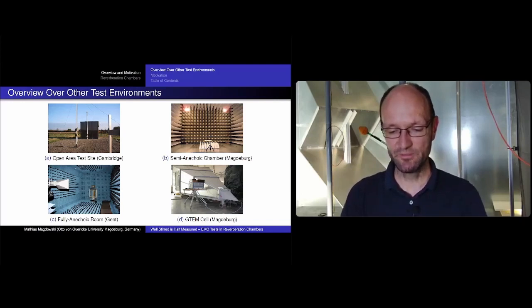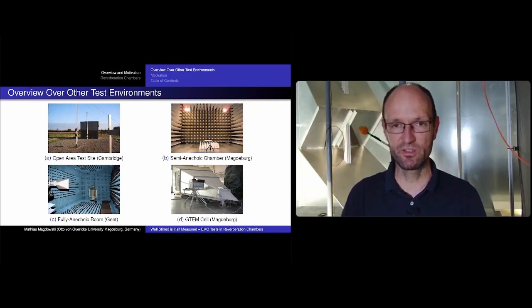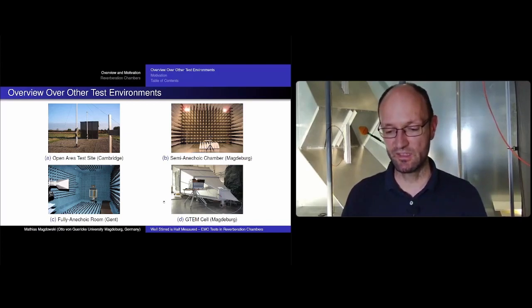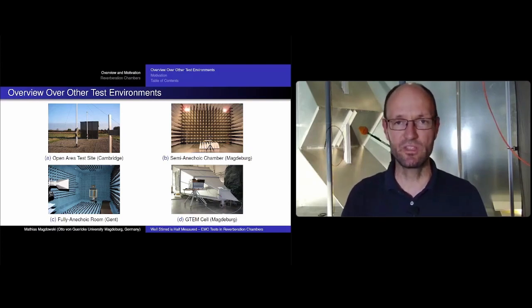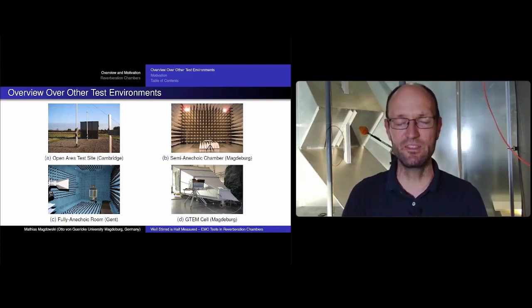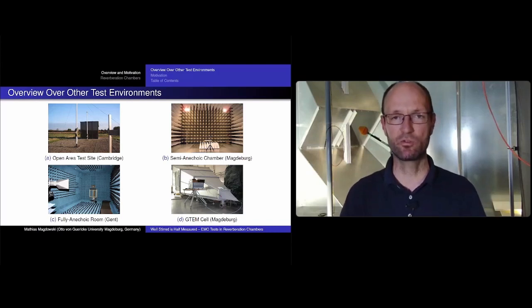There are also fully anechoic rooms — this picture is from Ghent University. They're typically used for antenna measurements and for EMC measurements above one gigahertz. Then there are TEM cells and GTEM cells; we also have a large one in Magdeburg. The common thing with all these test environments is that they measure in a directive way — you put your EUT and measure what it radiates in a certain direction, and you can also radiate onto it from a certain direction for immunity tests.